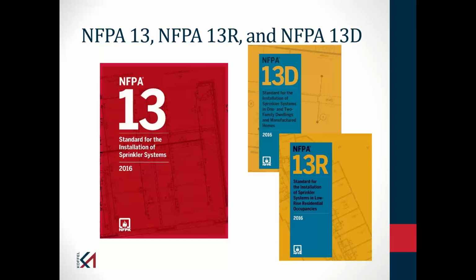It reduces the water supply. For a residential occupancy under NFPA 13, you need 30 minutes of water. For 13D, you need 10 minutes of water. If I'm using residential sprinklers in NFPA 13, I calculate 4 sprinklers flowing. In 13D, I typically calculate 2 sprinklers flowing. And 13D allows me to omit sprinklers from concealed combustible spaces, because the fatal fires tend not to occur in those spaces, but rather they tend to occur in the sleeping room, the living room, the kitchen. Those spaces we would be providing sprinkler protection. Now, what we saw as people started to become accustomed to 13D is that 13D systems were going in multifamily residences, like your dorms or multifamily apartment buildings.